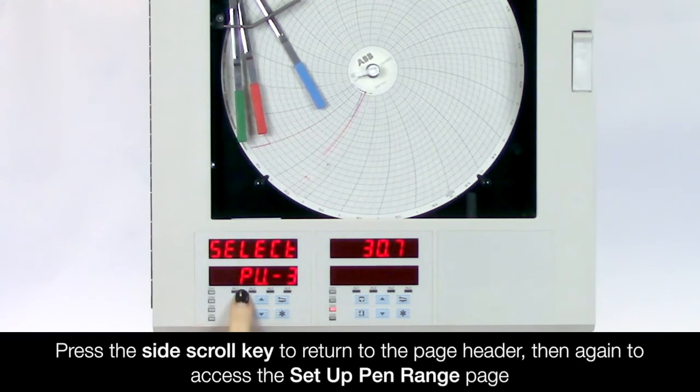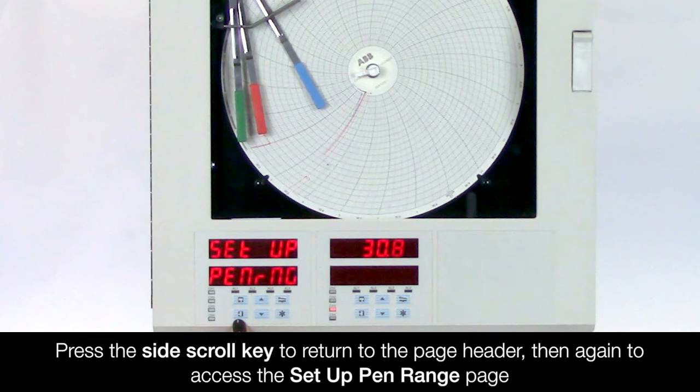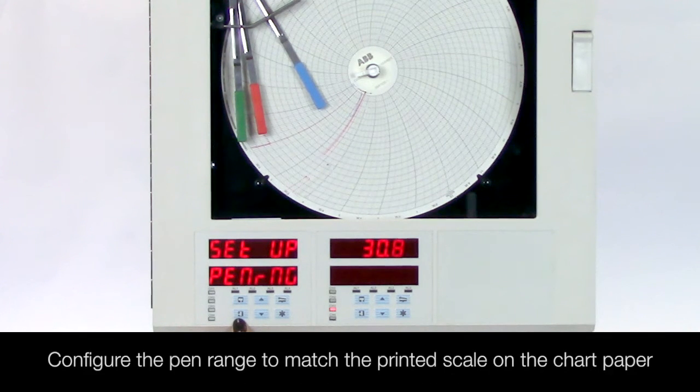When finished press the side scroll key to return to the page header and then again to access the setup pen range page. Configure the pen range you wish to record on the chart which should match the printed scale on the chart paper.